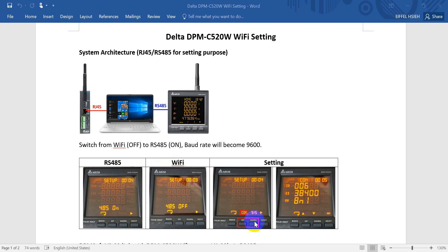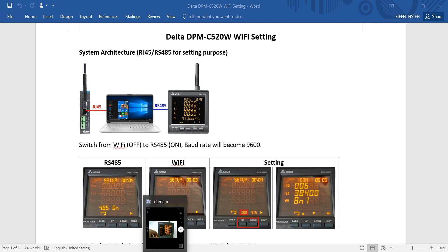If you want to set the protocol, you have to press the up and down button at the same time for around 5 seconds. Then you go to the COM setting, and you can set the ID, node address, baud rate, and parity check. I will show you how to set this up.